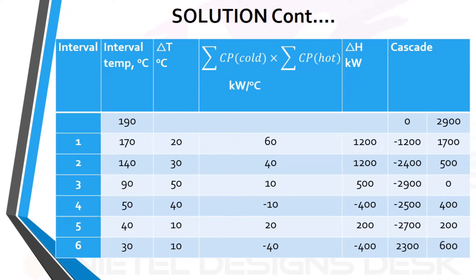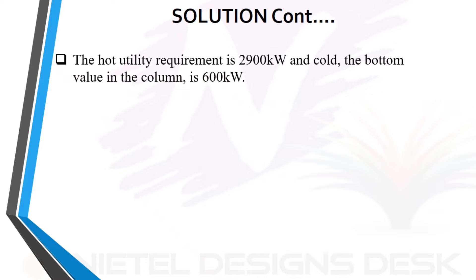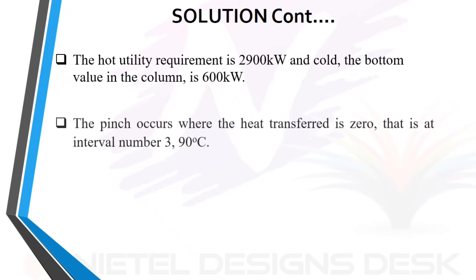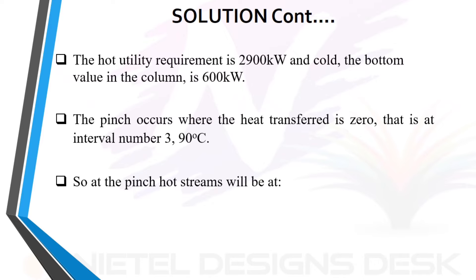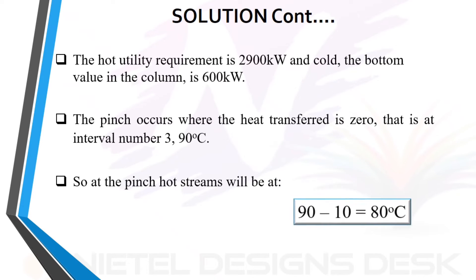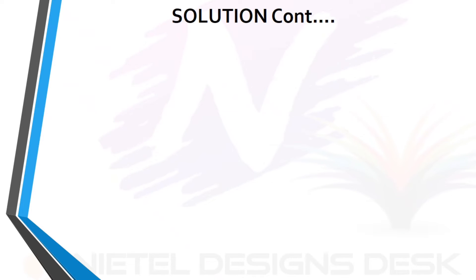In the last column, 2900 kilowatts of heat has been added to eliminate the negative values in the previous column. So the hot utility requirement is 2900 kilowatts, and the cold utility — the bottom value in the column — is 600 kilowatts. The pinch occurs where the heat transferred is zero, that is at interval number three, 90 degrees Celsius. At the pinch, hot streams will be at 80 degrees Celsius. To design the network for maximum energy recovery, start at the pinch and match streams following the rules on stream heat capacities for matches adjacent to the pinch.